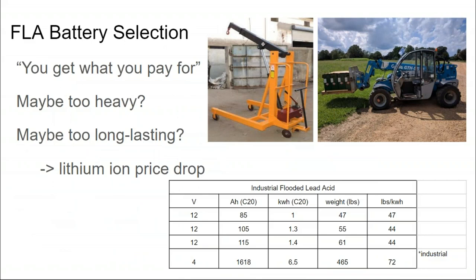Lithium ion, you don't have that option, all lithium ion batteries are sealed. So when you look at the charger settings of a universal inverter and select lithium ion technology instead of lead acid technology, it will actually reduce the charging parameters of the battery, restricting its maximum voltage to keep it within a safer operating range.